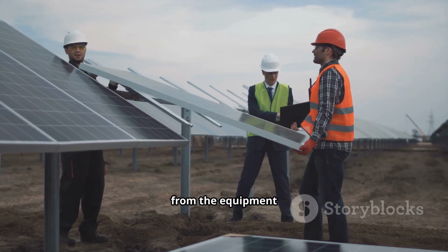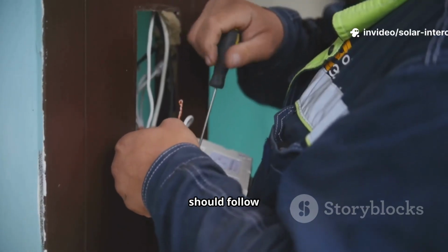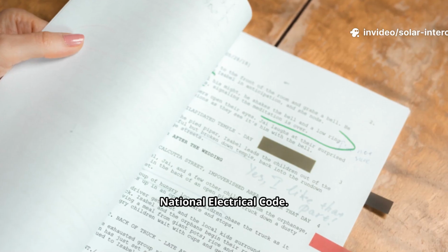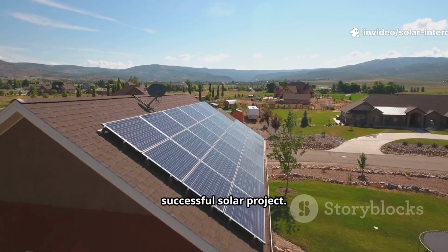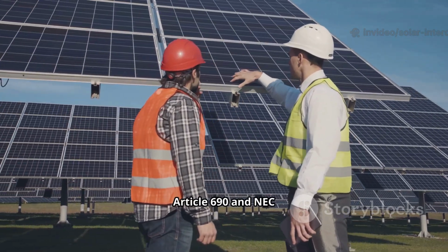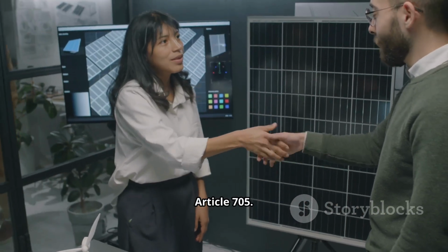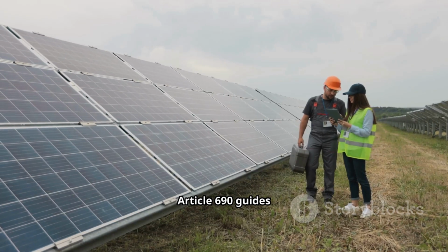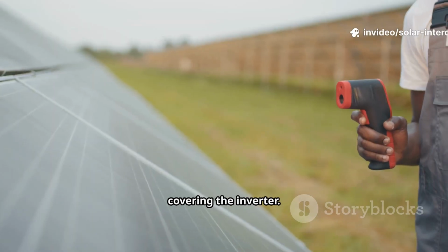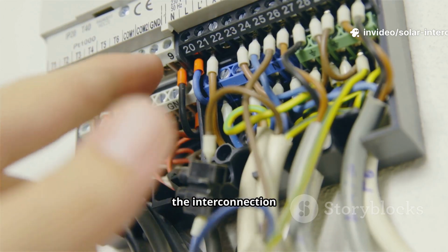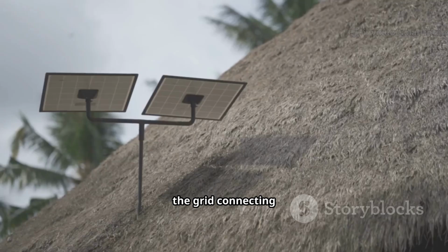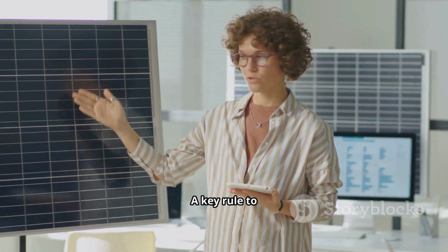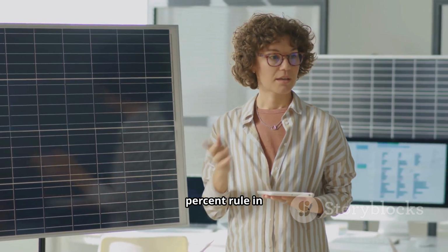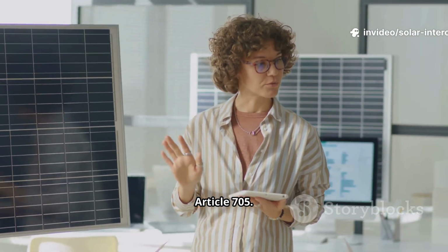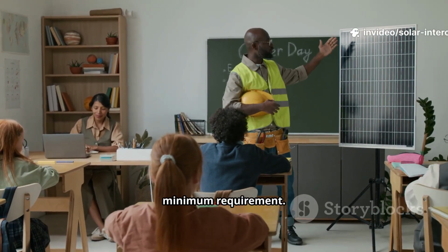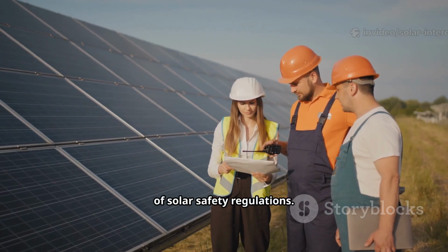Every decision you make, from the equipment you choose to the way you connect it, should follow safety and the National Electrical Code. This is the foundation of a successful solar project. Second, focus on NEC Article 690 and NEC Article 705. Article 690 guides the solar system, covering panels, covering the inverter. Article 705 guides the interconnection point, connecting to the grid, connecting to your home's electrical panel. A key rule to master is the 120% rule in Article 705. Understanding these two articles is the minimum requirement. They are the core of solar safety regulations.